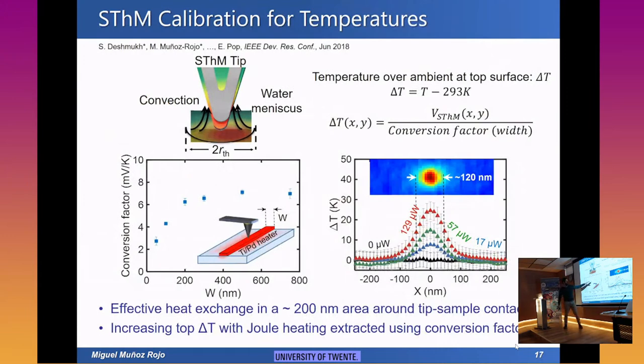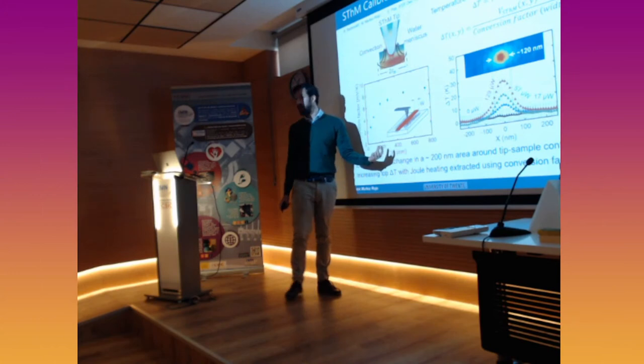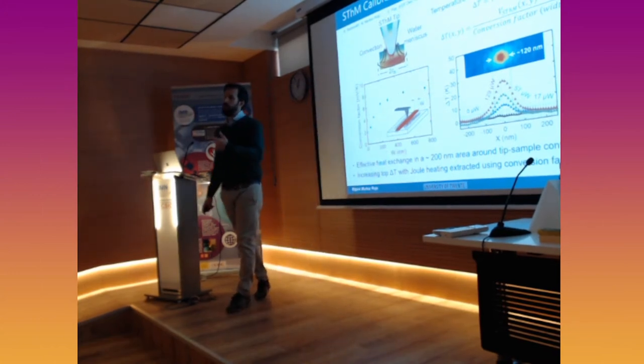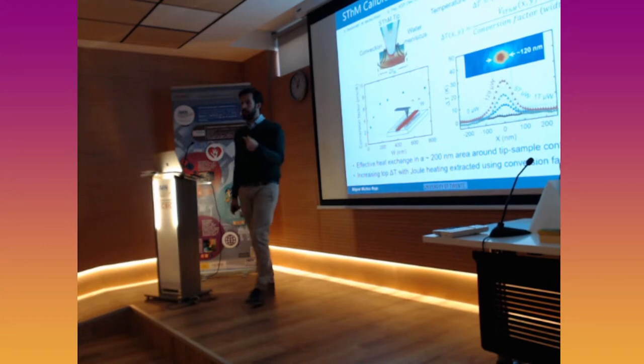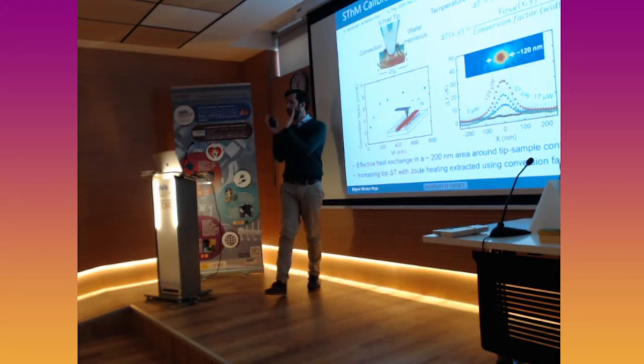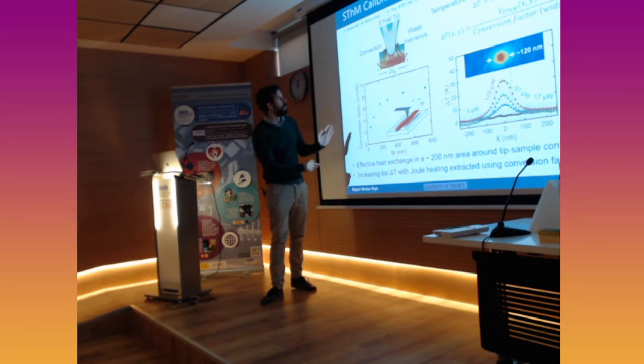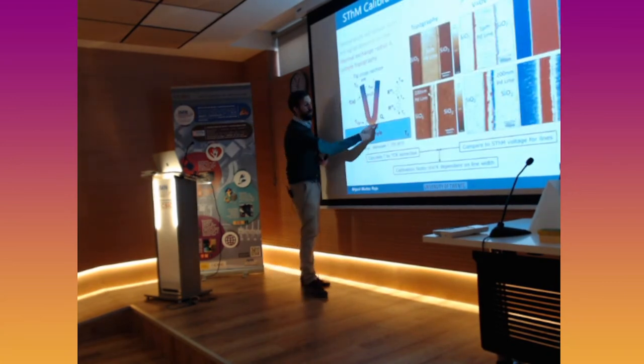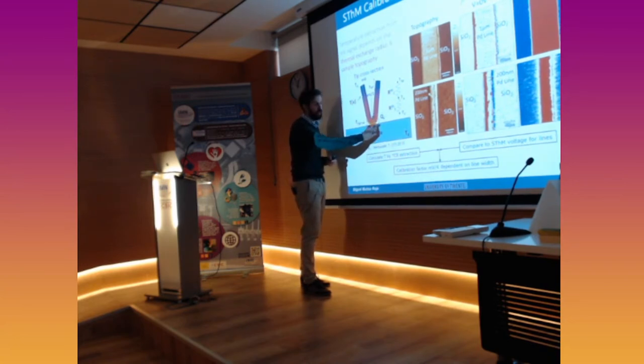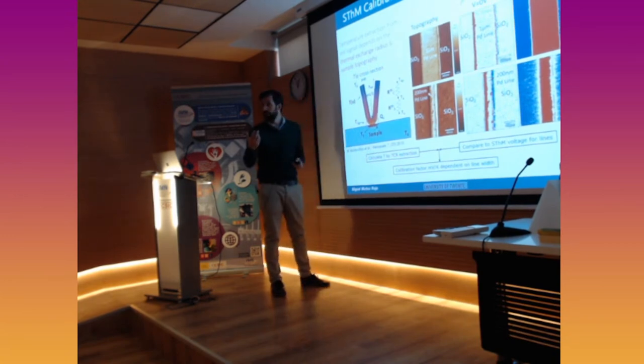Here, what you see is that the conversion factor is constant above a value around 200 nanometers. This corresponds to the width of the line. If you measure the thermal exchange radius between the probe and the sample surface—the standard approach, where you heat up the probe—this corresponds to this area. When I talk about thermal exchange radius, I mean the area in which the tip is exchanging heat with the sample. That's basically the radius.